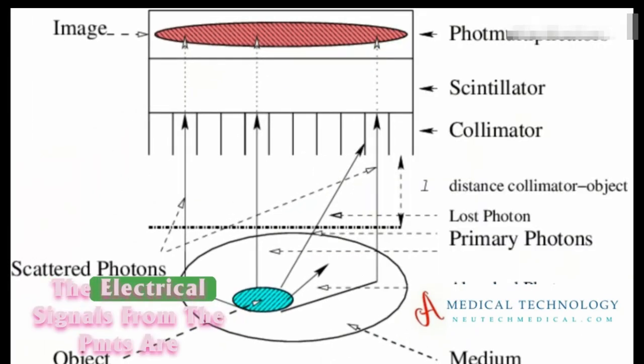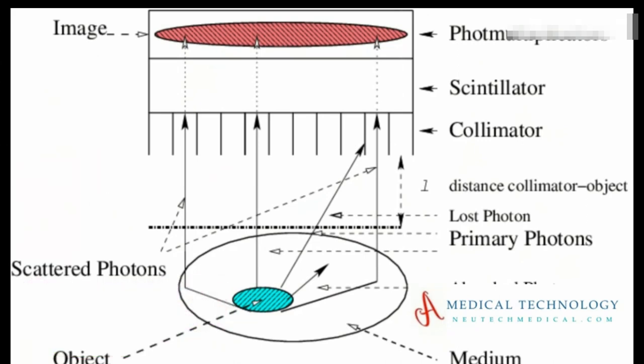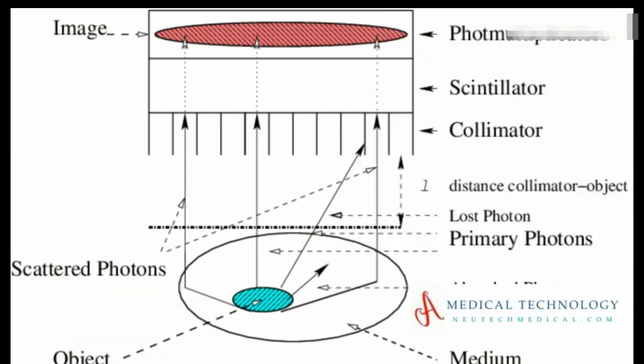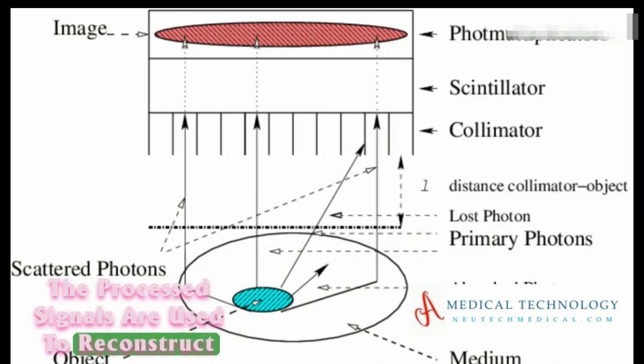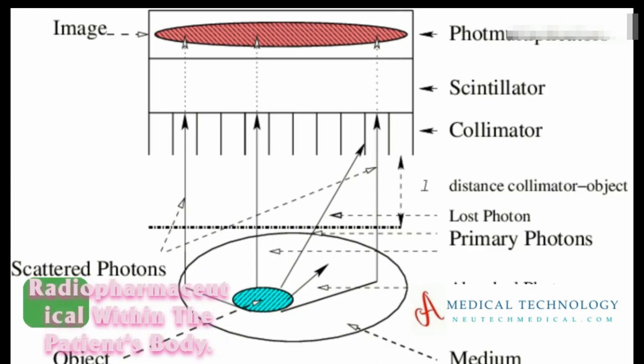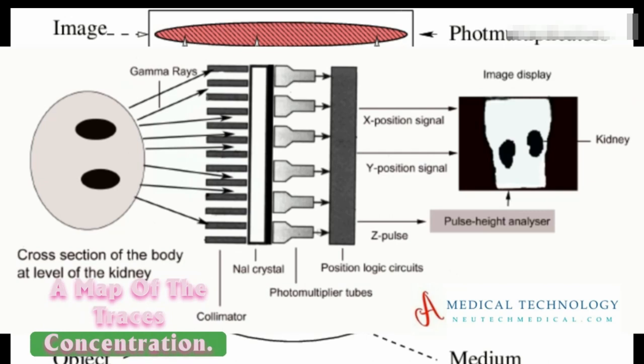Signal processing: The electrical signals from the PMTs are processed by the gamma camera's electronics. The position and intensity of each scintillation event are determined based on the signals received from the PMTs. Image reconstruction: The processed signals are used to reconstruct an image of the distribution of the radiopharmaceutical within the patient's body. Each point in the image represents an area where gamma rays were detected, providing a map of the tracer's concentration.